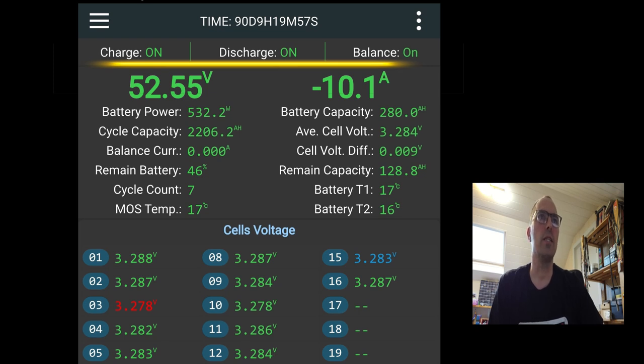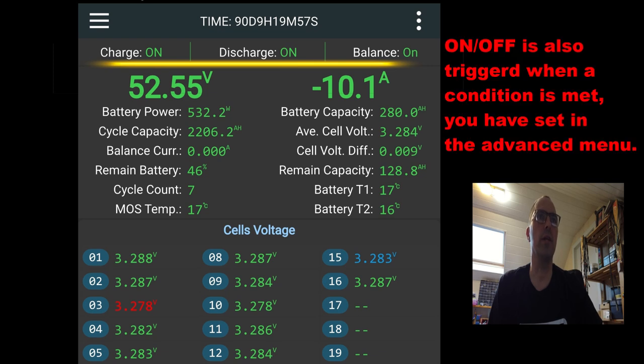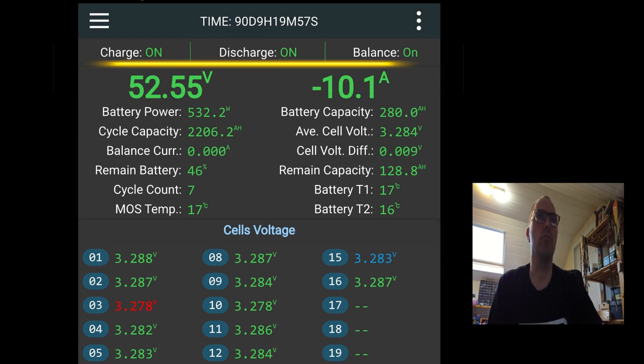I see one reason where you can switch off the balance. That's when you want to attach an external balancer. If your cells are completely out of balance, maybe you need a higher current balancing system. But in general, standard, they're always on.